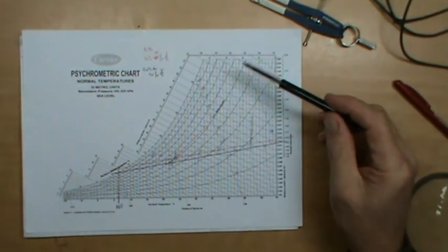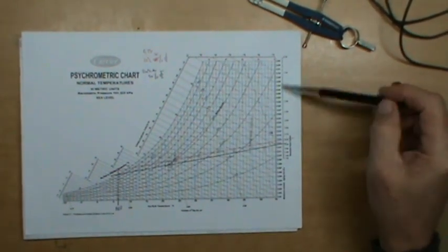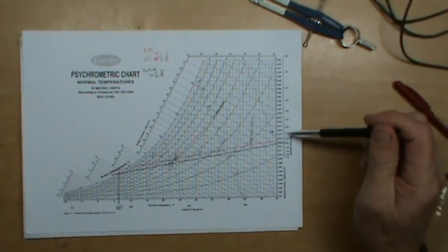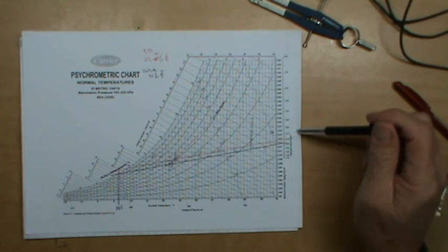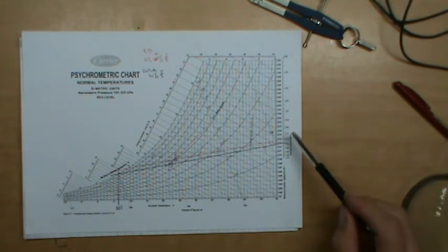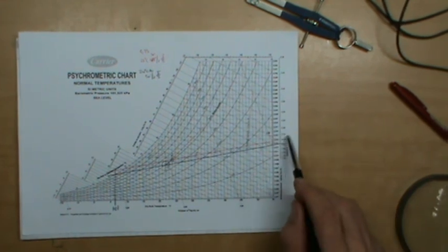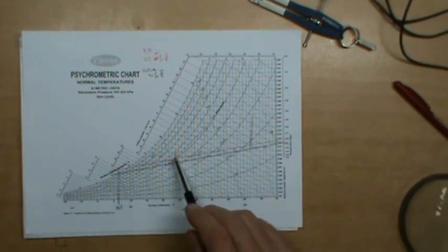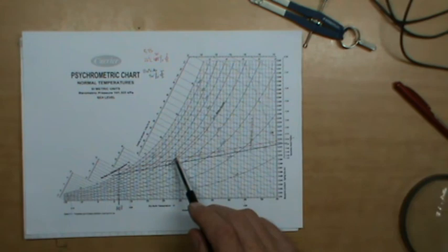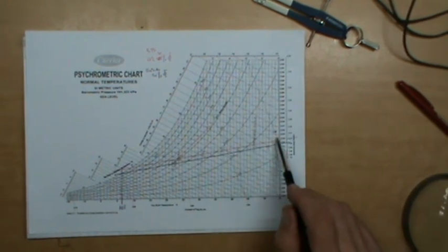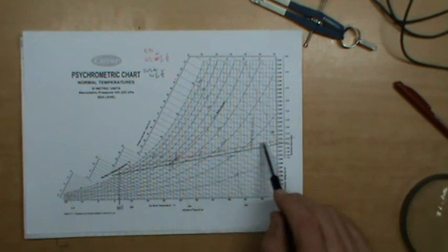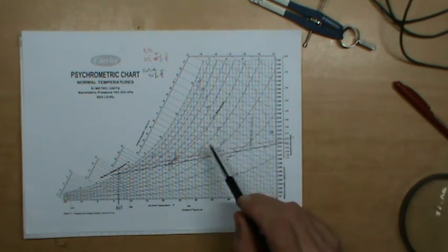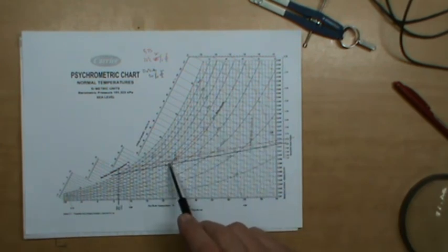You'll do the rigmarole in terms of the calculations to determine your sensible heat factor, your effective room sensible heat factor, and then you're going to draw a line from the effective room sensible heat factor, which in this particular case is the red line, through that swivel point that you would have put on your psychrometric chart if it was not supplied.